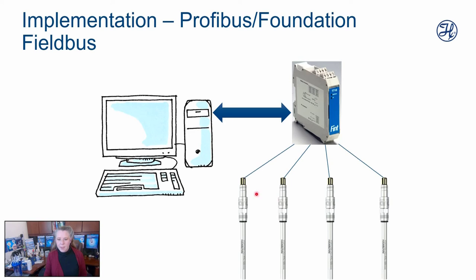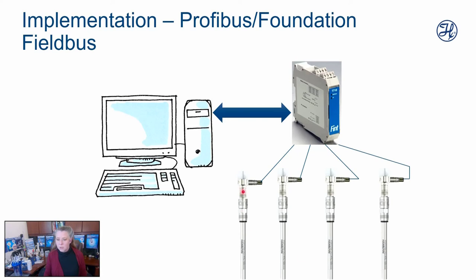And within these, you can have maybe one card that controls multiple probes. You can even do Bluetooth connections in these. You can have OPC that goes to a computer type system. You can have Modbus. All of these are really robust digital signals that allow you to get more than just a signal. An analog probe only gives you the signal, your DO measurement, maybe as a millivolt, maybe as a nanoamp. It only gives you a pH measurement. It doesn't give you anything else.